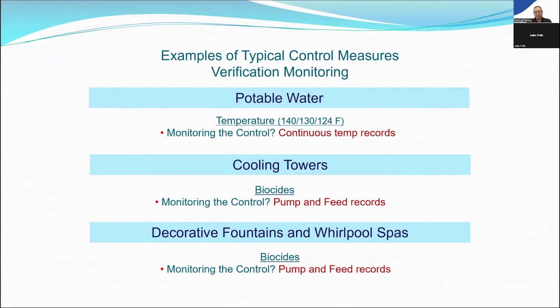Your verification goes through known norms of what your temps are. We know that at 140, we're going to kill off Legionella virtually instantaneously. At 130 degrees Fahrenheit, we can really limit that growth. That's at the top end of its growth, but it really likes growth in the 120 ranges, and we know we can't deliver above 110 for scalding precautions. So oftentimes we're having very warm water tanks at 140 plus, so that we're killing off the Legionella in there, and then they're going through a mixing valve to get down to that 110. The closer that mixing valve is to the delivery point, the better off you are, because the less run you have of that 110 temperature water that can be an issue.